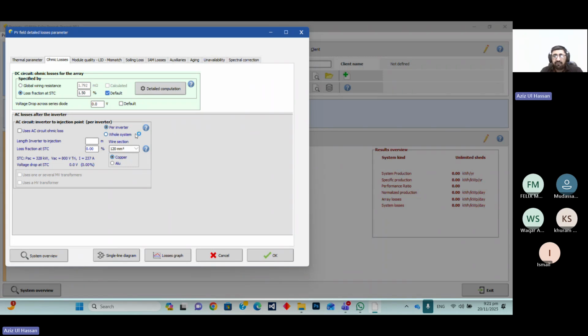Okay. Now, what is your duty when you are doing your PVsyst? You have to do the cable sizing first, as per the actual length, as per the site, as per the vendor data, and find the total average loss of your solar system. And then you should put that value in your simulation. But you have to give some margin in your losses.